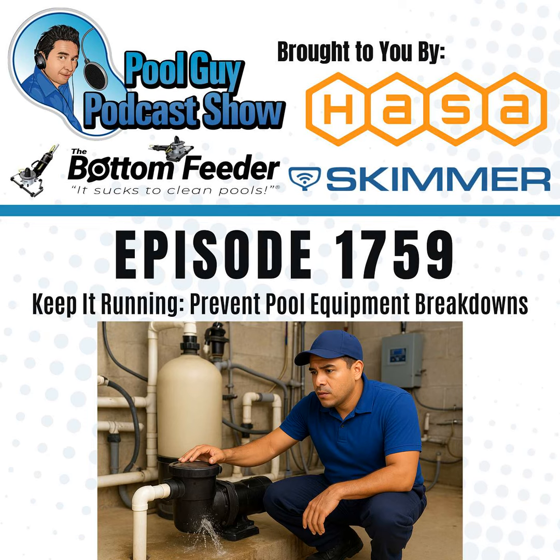Let me move on to pumps. Pump leaks are very common as well. As the pump gets older, you may see a leak from maybe the seal of the pump underneath, and this is very common. If you look at the pump, you kind of get down and look at it from underneath, and you see water dripping from the center of the motor, more than likely that's the pump seal, and that's probably what you're going to have to replace to get the leak to stop. It's not something that is going to be simple. You have to take the motor apart, take the impeller off, and put a new seal on.